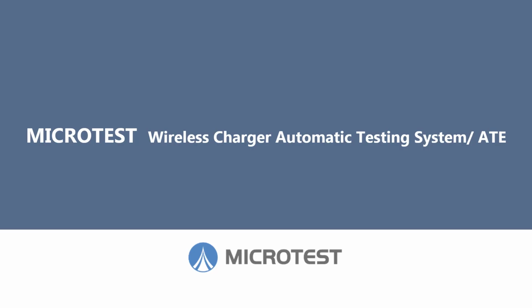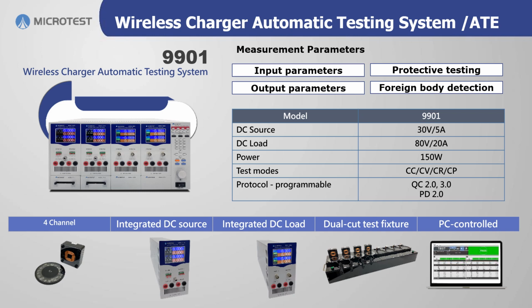Now let's dive into the world of automatic test system for wireless charger. The Microtest 9901 wireless charger automatic testing system is designed specifically for automated testing for wireless charger products. It provides 4 sets of test channels and integrates electronic loads with DC power supplies. Under dual-cut fixture testing, it achieves high efficiency measurements. The entire system can be controlled through PC programming, comparing input-output, protection testing, and foreign object detection. It is capable of testing products up to 150 watts.